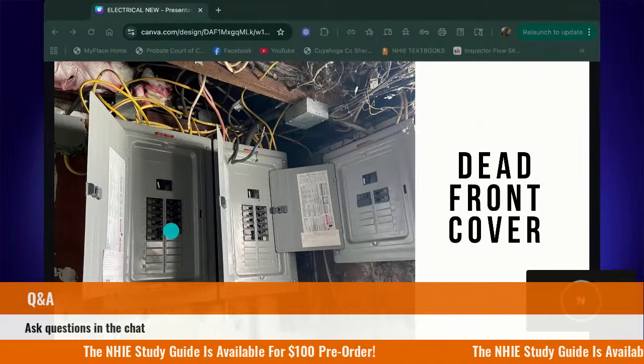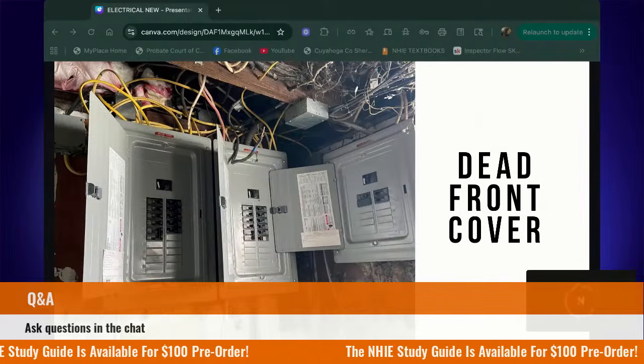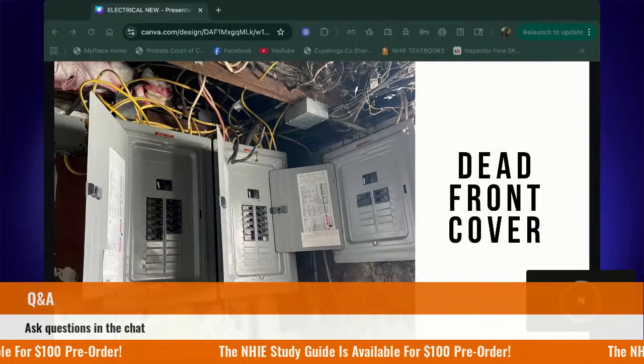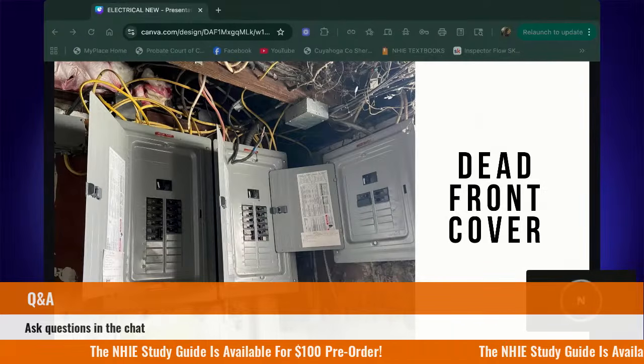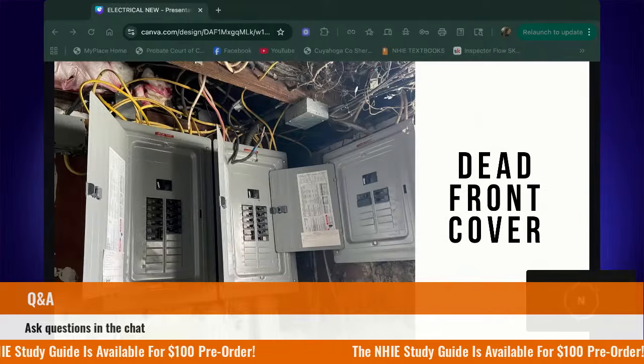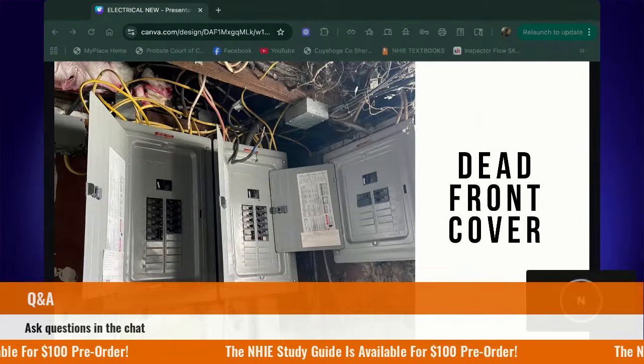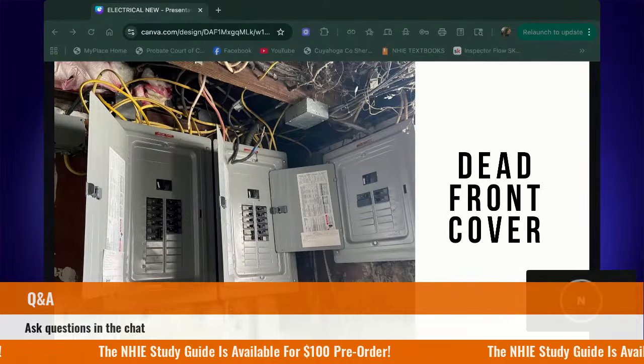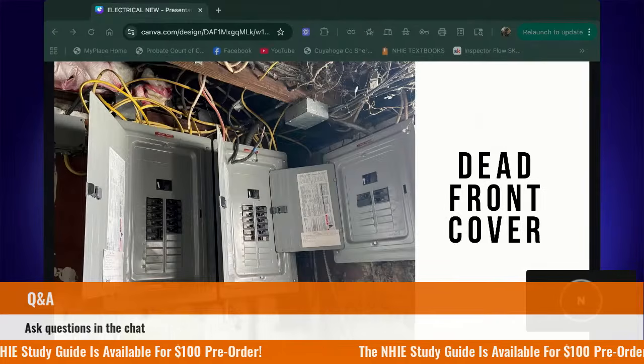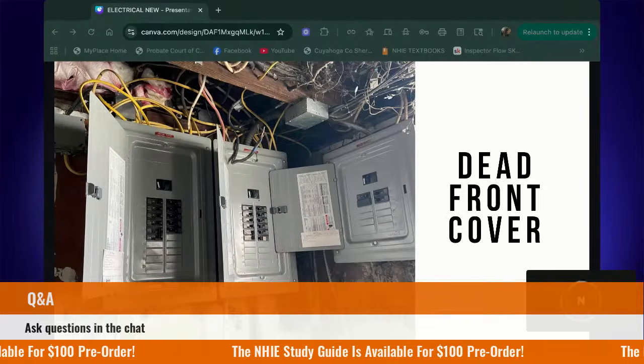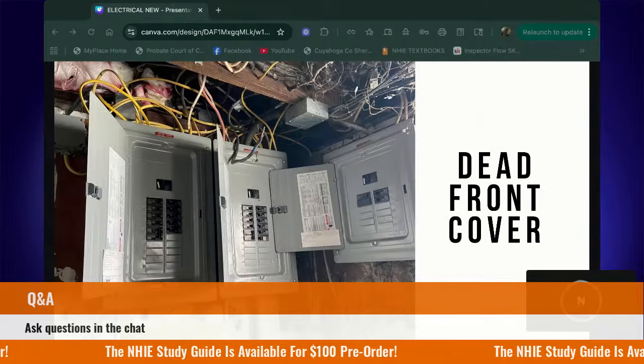And then when you do remove the dead front cover, you've got to listen. Do you hear any buzzing? Do you see, again, any signs of arcing, which is basically overheating, the step before fire? All of this stuff may suggest that the panel may be unsafe. So you've got to really pay attention when you are removing the dead front cover.